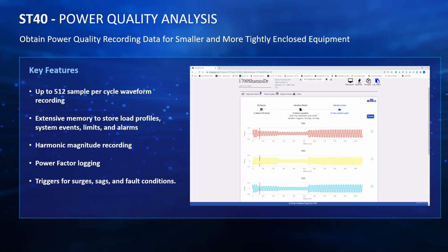And in addition to the waveform capture capabilities, we can set up limits on any parameter the meter can monitor. So total harmonic distortion, individual harmonic magnitudes and angles, power factor, frequency, demand, all of that can be set up as a limit and can alert you if not necessarily you're coming into a power quality event, but if you're reaching your peak demand, you can be alerted ahead of time so that you can make moves to reduce demand.